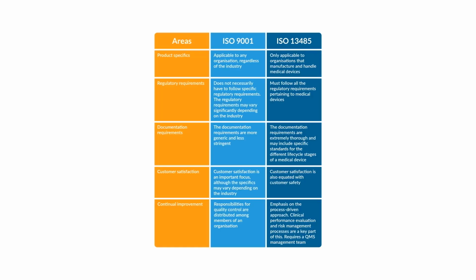If you are compliant or certified, you are most likely also compliant for the majority of the ISO 13485 medical device standards, right? But you still have to comply with a few more regulations of your land, specifically in India, like CDSCO and other norms, to make sure you are totally compliant, right? So, just a quick demarcation into the differences, or comparisons, between ISO 9001 and 13485.